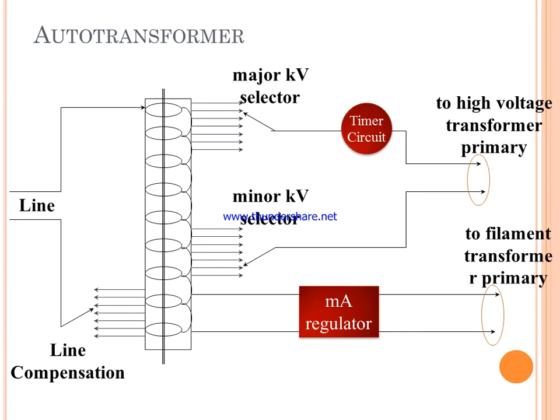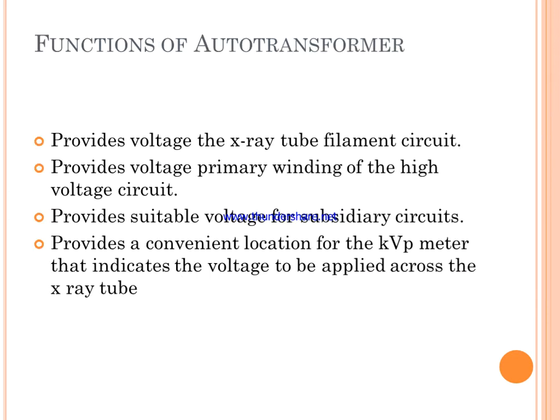The auto transformer functions as both a step-up and step-down transformer. Here is an image of the auto transformer showing line compensation, a major kVp selector, and a minor kVp selector, which connect to a timer circuit and high voltage transformer primary.